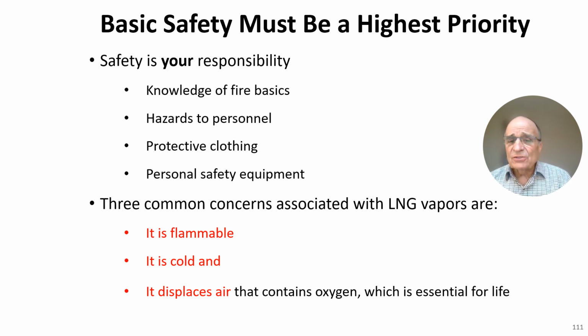Three common concerns associated with LNG and LNG vapors: the vapors are flammable. The LNG itself is not flammable, but the vapors are flammable when mixed with air, with oxygen. LNG and its vapors are cold. Breathing in cold LNG vapor can blister your lungs. Breathing in LNG vapors, aside from being cold, means a lack of oxygen, which can asphyxiate, because it displaces air. So the three concerns are flammability, its temperature, and its ability to displace air.